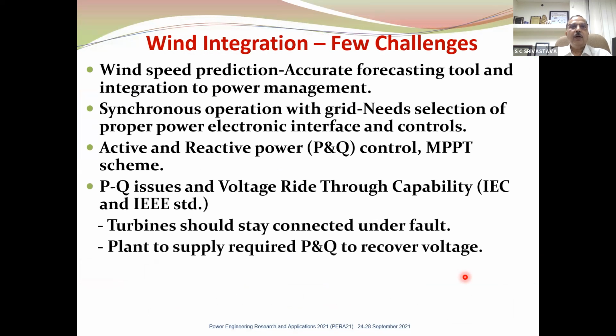Now let me take the example of wind and solar - what challenges do they independently pose? Wind speed prediction needs accurate forecasting tools, power management tools, and synchronous operation, since they normally employ non-synchronous sources of generation. That is possible through good power electronic interfaces and controls - active power and reactive power. If induction generator support is not there, they will consume reactive power instead. So how do you address that?